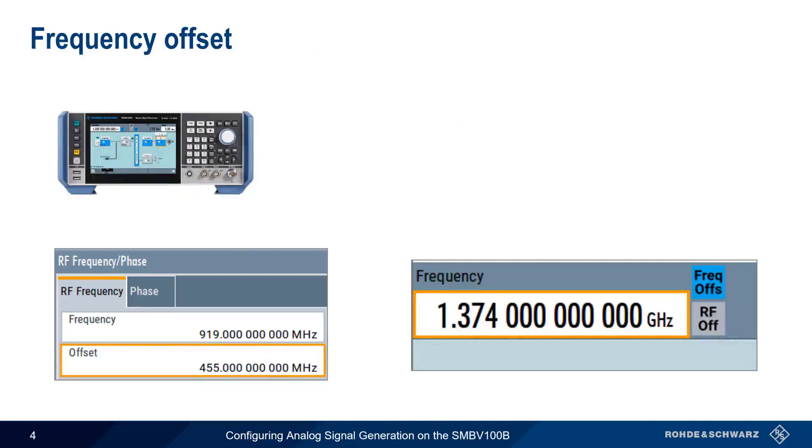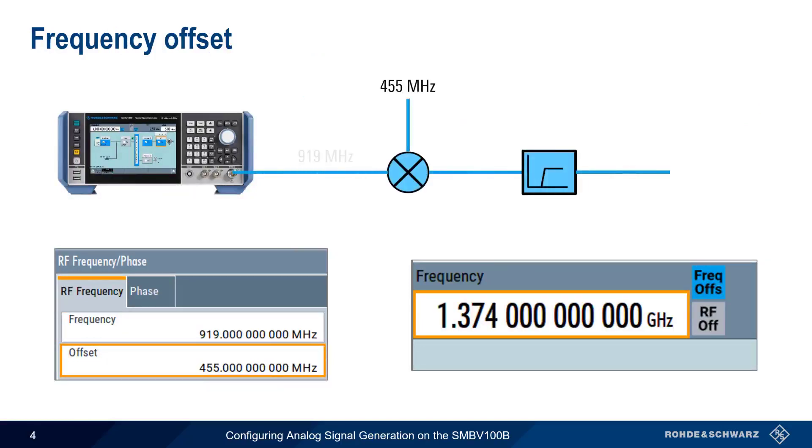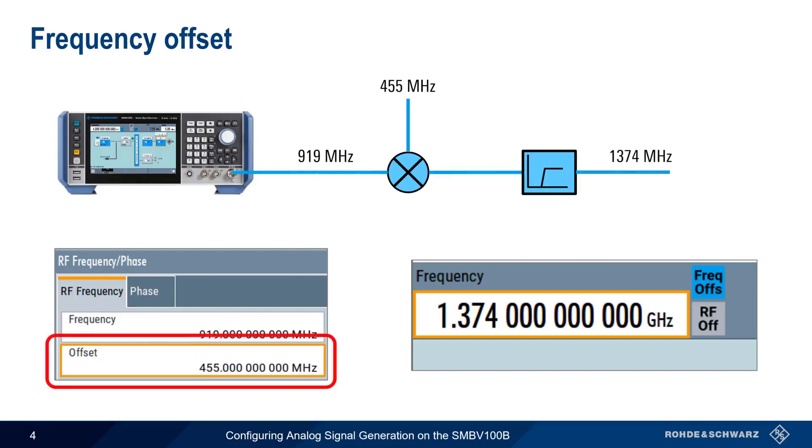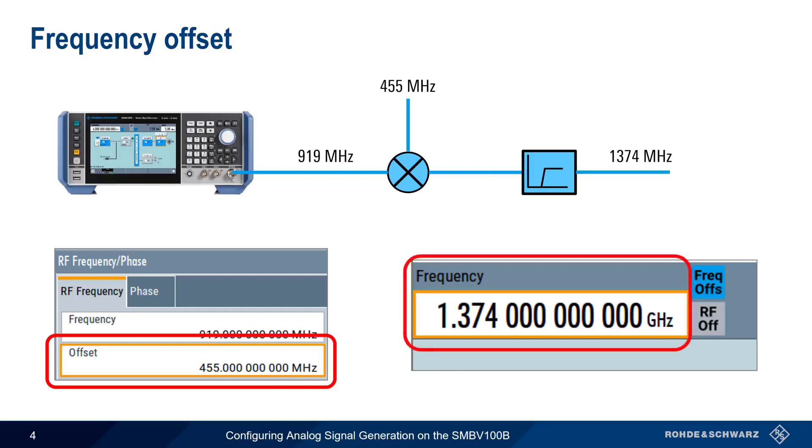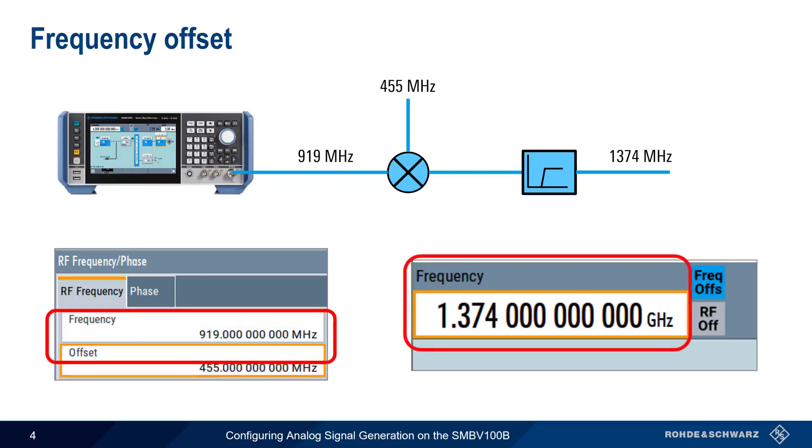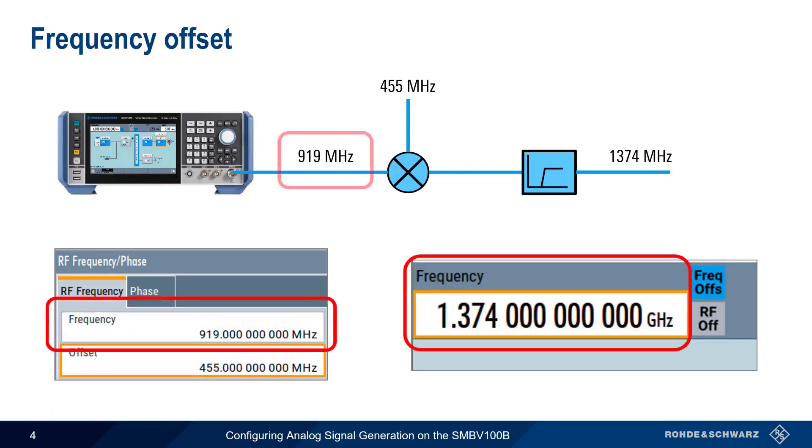A Frequency offset can be useful when there's a downstream frequency shifting device, such as a mixer. Entering an offset changes the frequency value shown in the status bar. Here we add 455 to 919 and get 1374 MHz. Note, however, that the actual SMBV output frequency does not change.